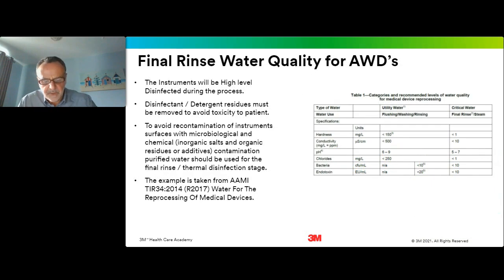So if we look at the final rinse water quality required for automated washer disinfectors, this table, which is taken from the US TIR34, shows you a column for two different types of water. The first is utility water, and you can see here the levels of hardness, the conductivity, the pH, the presence of chlorides, which are usually controlled because chloride ion will even attack stainless steel and corrode it. And then, of course, we consider bacteria and endotoxins.